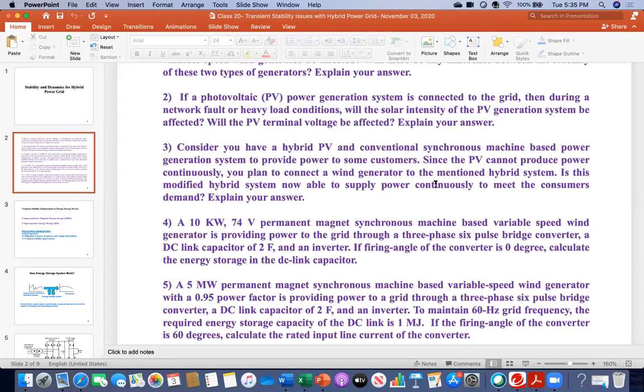If you look at the structure of this hybrid system, connecting PV and wind means both are fluctuating sources. So connecting wind can meet the magnitude of demand, but you might still get fluctuated output power, voltage and frequency - everything fluctuating. That's why you must connect an energy storage system, which will compensate, mitigate or suppress those fluctuations. So the appropriate answer is yes, this modified hybrid system is now able to supply power, but only with the energy storage system, which is needed to meet the consumer's demand.